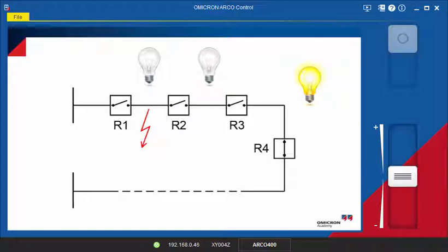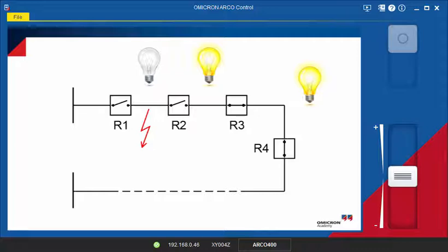With the closing of R4, R3 detects voltage recovery on its load side. R3 then closes after its configured close time to restore the power supply for customers between R2 and R3.